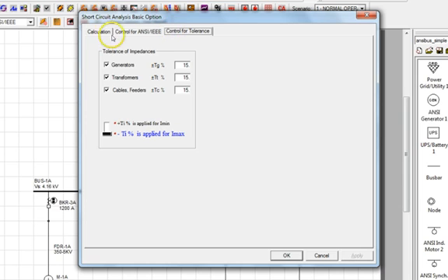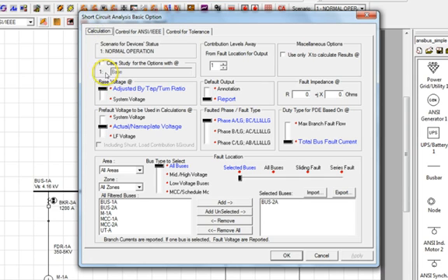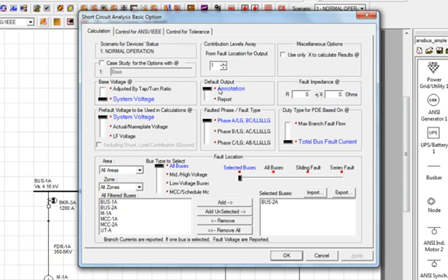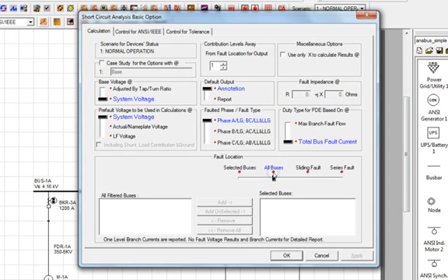Let's go to the Calculation tab and select the system voltage as our base and pre-fault voltage for the analysis. Annotation will be our default results output. This basically means that we will display the results of the analysis on the single line diagram instead of using a written report. Lastly, for this section, we'll choose all buses as our fault location.